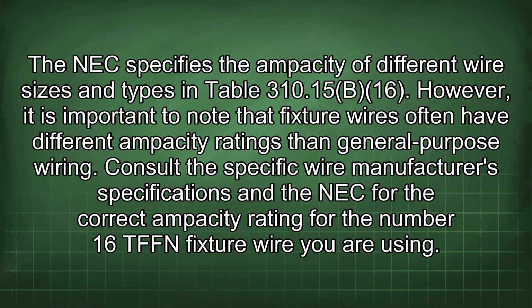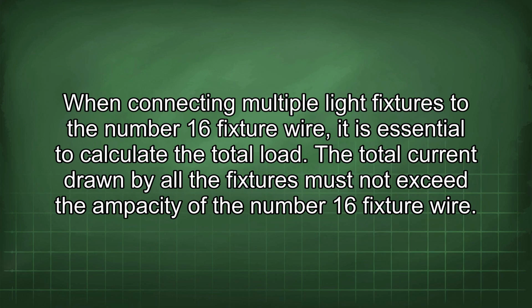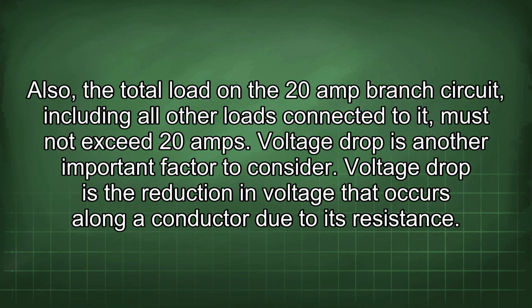310.15(B)(16). However, it is important to note that fixture wires often have different ampacity ratings than general-purpose wiring. Consult the specific wire manufacturer's specifications and the NEC for the correct ampacity rating for the number 16 TFFN fixture wire you are using. When connecting multiple light fixtures to the number 16 fixture wire, it is essential to calculate the total load. The total current drawn by all the fixtures must not exceed the ampacity of the number 16 fixture wire. Also, the total load in the 20-amp branch circuit, including all other loads connected to it, must not exceed 20 amps.